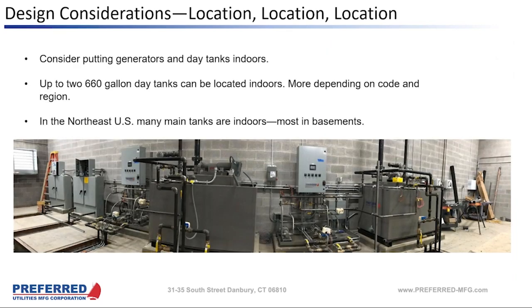Yep, absolutely. Okay, so consider putting generators and day tanks indoors. This is the best protection from the elements. And NFPA allows you to do two 660-gallon day tanks indoors before you have to go to a special fire-rated room. Indoor fuel oil equipment is much more common in the Northeast U.S. than it is in the rest of the country, because the big cities in the Northeast just don't have any room outside for their diesel systems. Whereas out west here where I work, it's very rare to have diesel inside of a building. Our gensets and our main storage tanks and our pump sets are usually all outside.